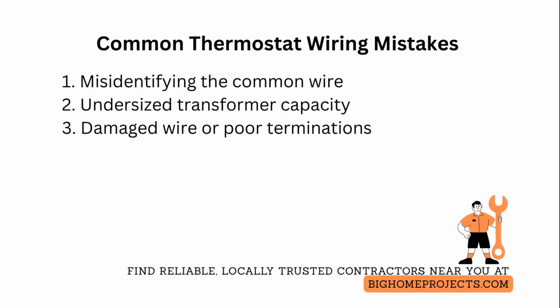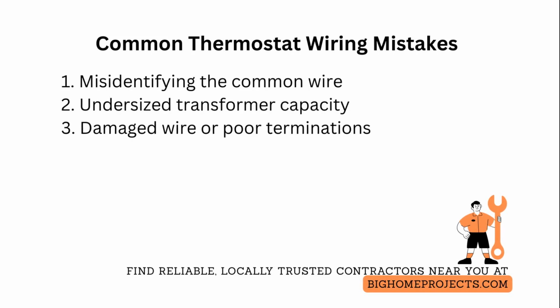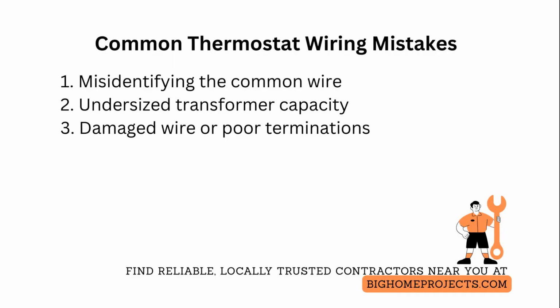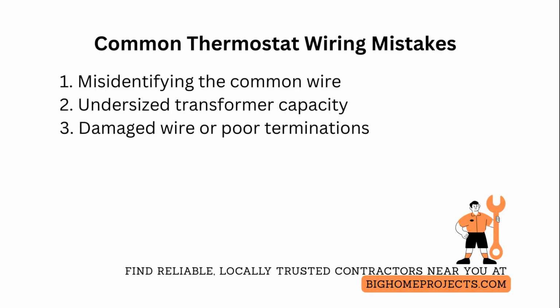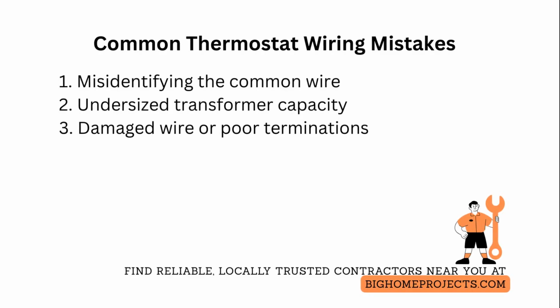One of the third errors is using thermostat wire with damaged conductor insulation or improper terminations at the condensing unit, producing intermittent contactor operation. Prevent this by using new 2-conductor cable, proper crimped or screw terminals, and sealing outdoor terminations against moisture.